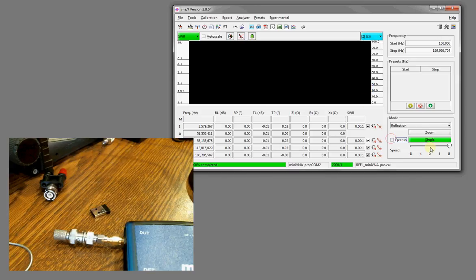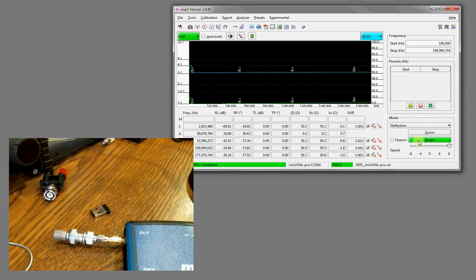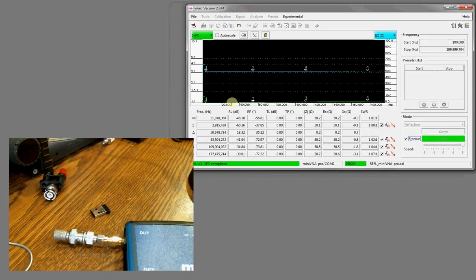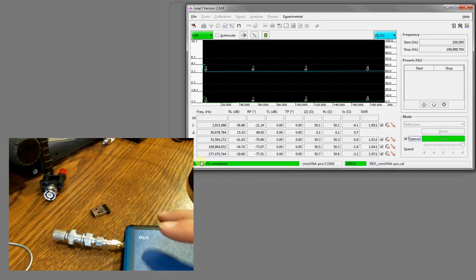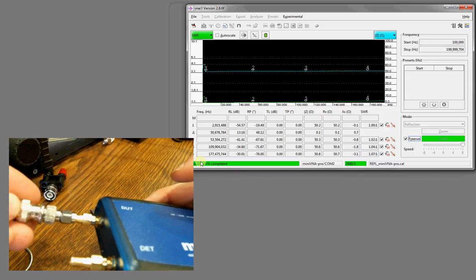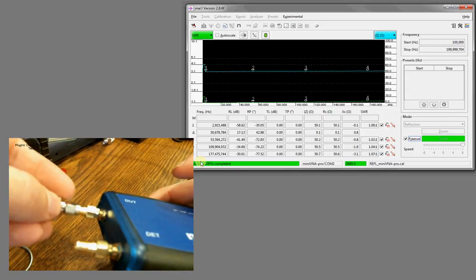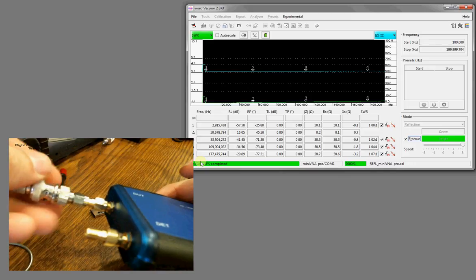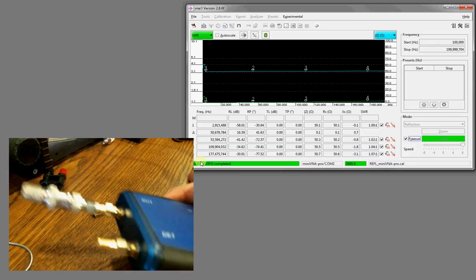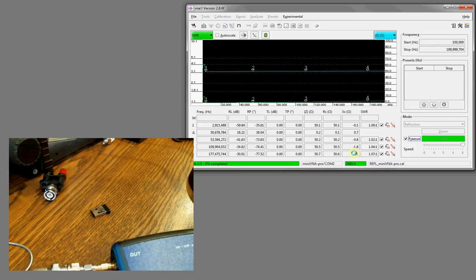And if we do a free run, or let's do a single pass at 8, and we'll do free run, you'll see that through the software it keeps doing the test over and over. So if I put my hand on it or something, you can see slight changes. It's not the best thing to show you this on, and by going fast with the speed you're getting measurements, but they're not as accurate.